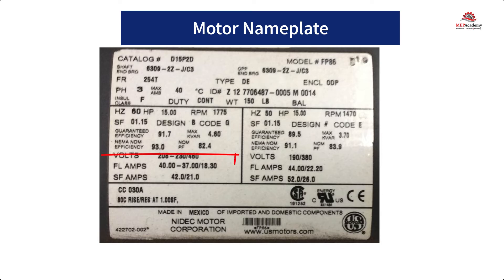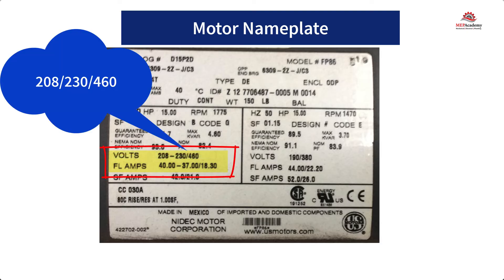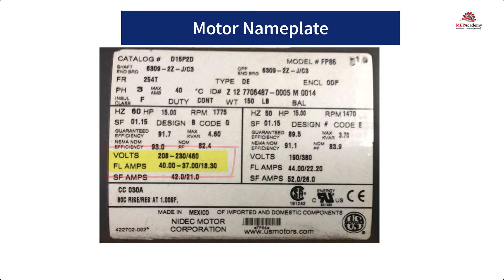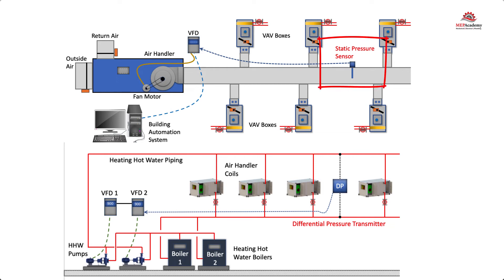The values shown here are for this example motor nameplate. You need to know full load amps — in this case, the nameplate shows 40, 37, and 18.3 as the full load amps. Each of those three numbers is represented by the voltage, which is either 208, 230, or 460, and the horsepower being 15, the speed, the RPM being 1775. Another thing to think about with your variable frequency drive is what's going to control the drive. We showed two examples: one was a static pressure sensor for airflow, and the other was a differential pressure transmitter for water flow.